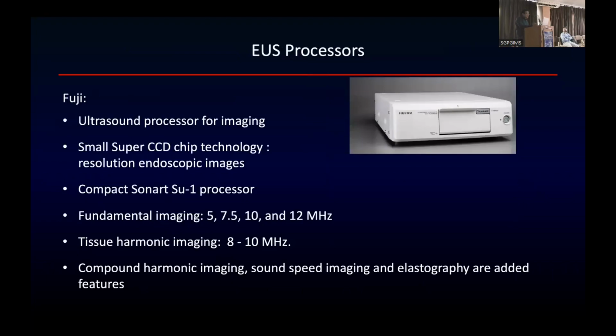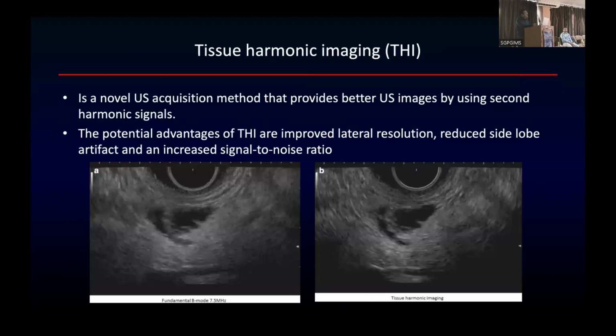Now the processors. There are certain features which each company claims about the processors they have used. I have put this up, it may not be essential to remember. This is a super small, super CCD chip, which is available. THI, tissue harmonic imaging, I have mentioned in EUS processors by Fuji, but this is now available with Olympus as well as Pentax. Tissue harmonic imaging is a term you need to know. What does it mean? You are playing with the harmonics or the waves generated in ultrasound imaging. It's a novel ultrasound acquisition method that provides better ultrasound images by using second harmonic signals. This is the principle of THI.